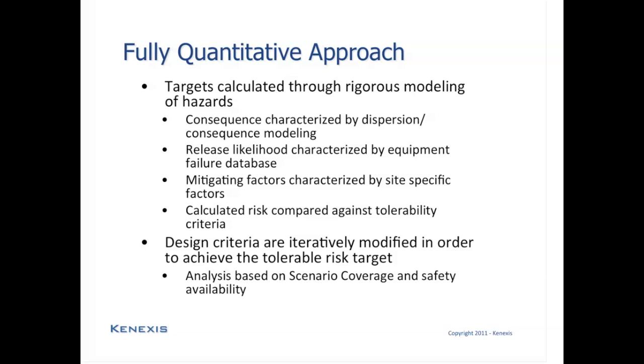And the analysis will result in either a tolerable level of risk being achieved, or, if the tolerable level of risk is not achieved, the fire and gas system design will need to be modified, trying to identify the weak points in the design, and then reanalyzed in a recursive fashion until the tolerable risk levels have been achieved.